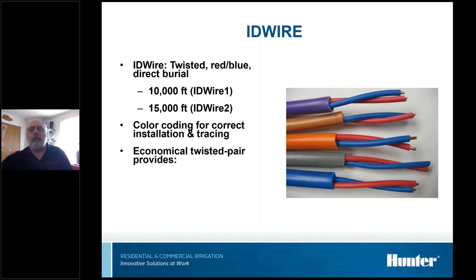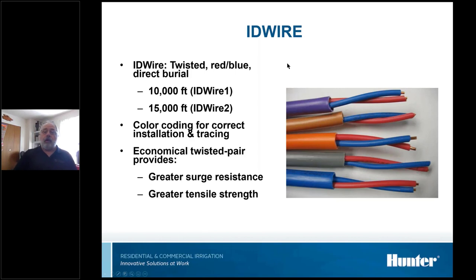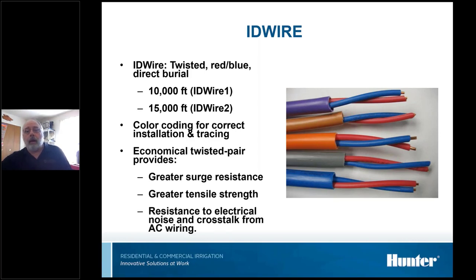And there's some unique stuff about it. Main thing, the wire is twisted inside that jacket. It does 3 things for us. The big one is it helps with suppressing surges. Anytime you twist wires, it makes it less desirable for electricity to flow down. And so what we're trying to do is get the surge to go into the ground rod. So we're trying to discourage it by twisting the wire. Anytime you twist any 2 filaments together, you make them stronger than the 2 by themselves. So it's stronger. And anytime you twist wires, it helps with electrical interference. And keep in mind that all this stuff is basically, we're burying little microprocessors out in the ground. So electrical interference can be a problem with these systems.